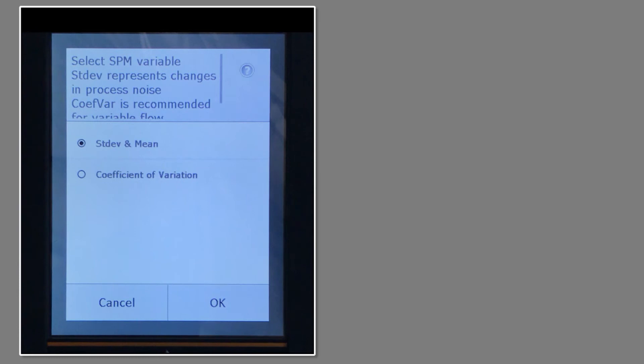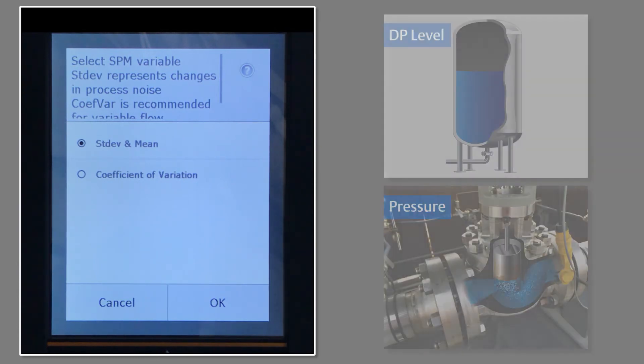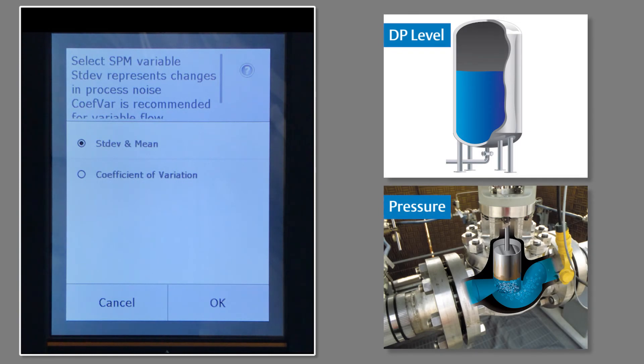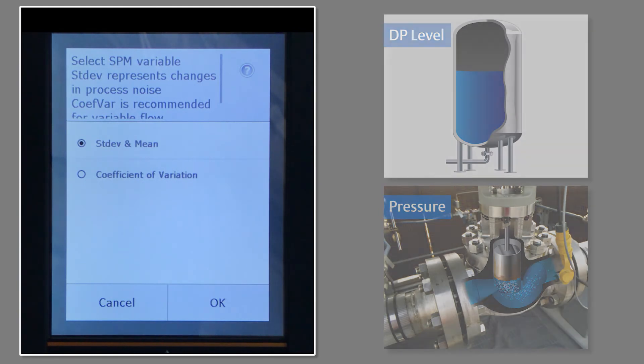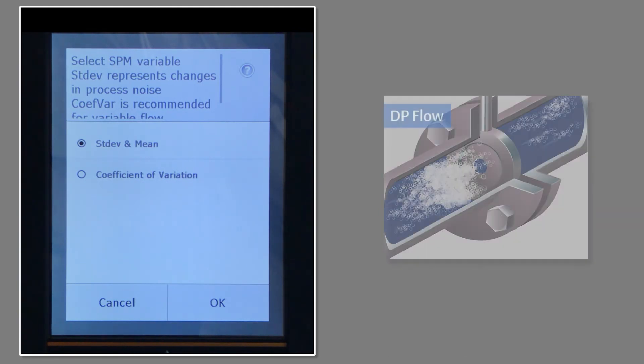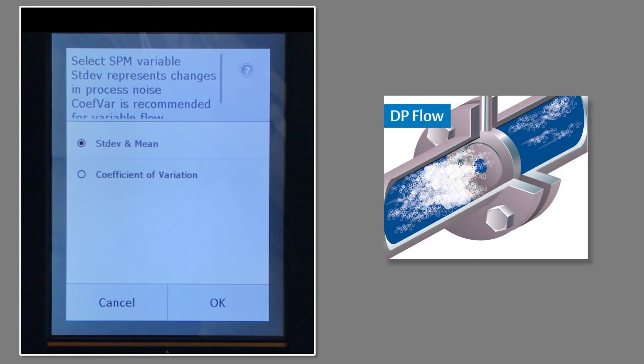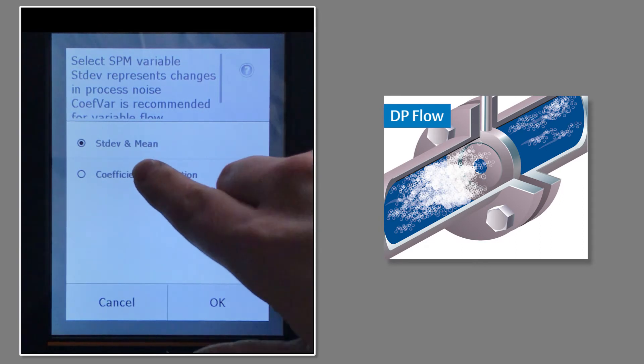Now, the SPM variable menu gives us two selections. Standard deviation and mean works best in level or pressure applications where coefficient of variation works best in flow applications. Since I'm working with a flow application, I'll select coefficient of variation.